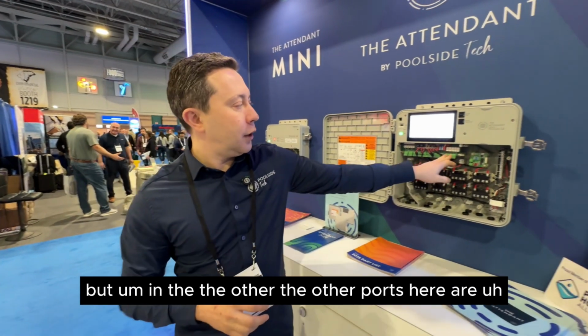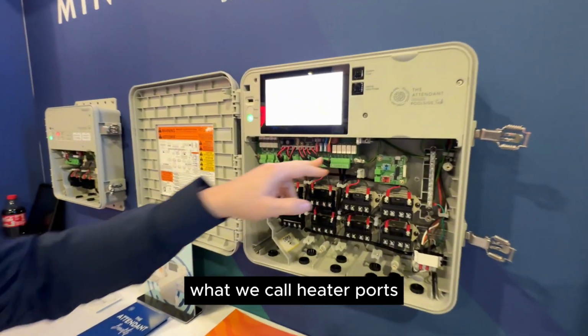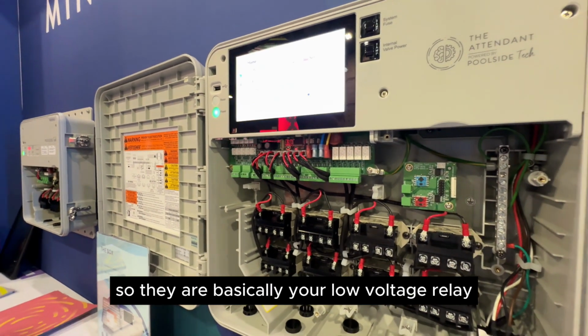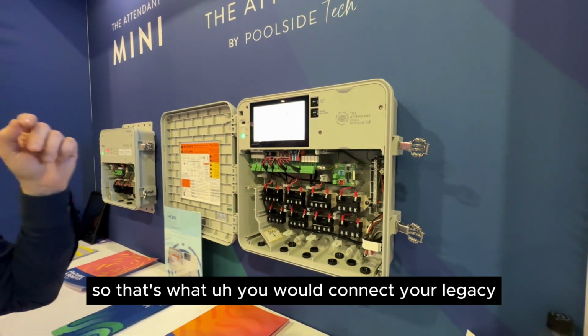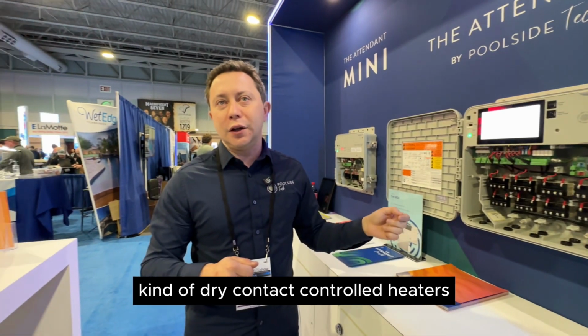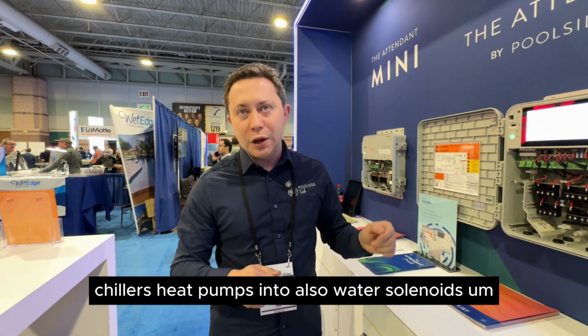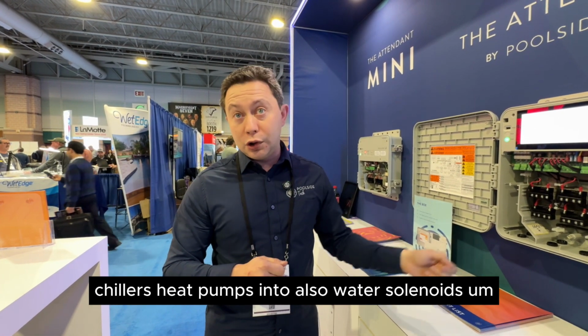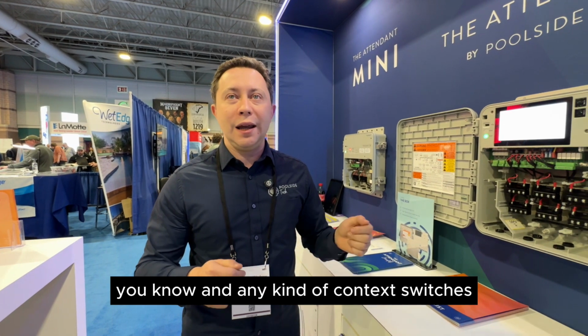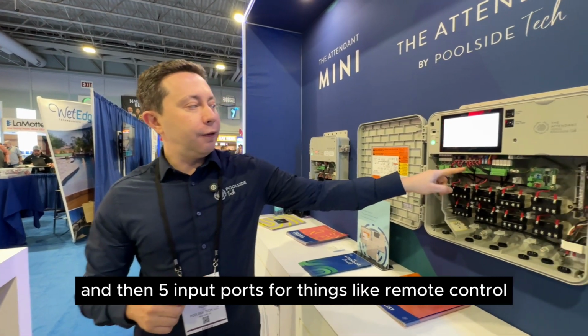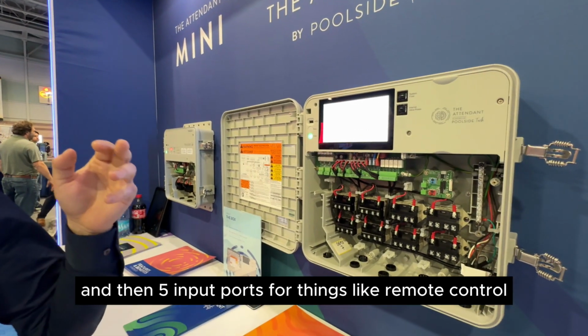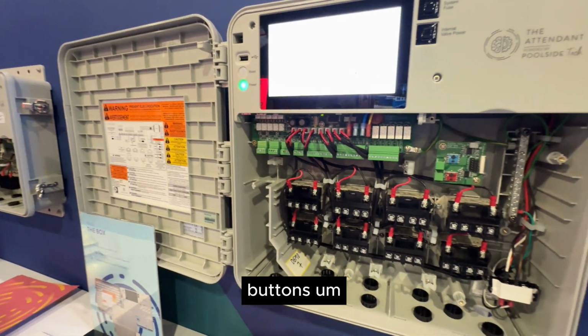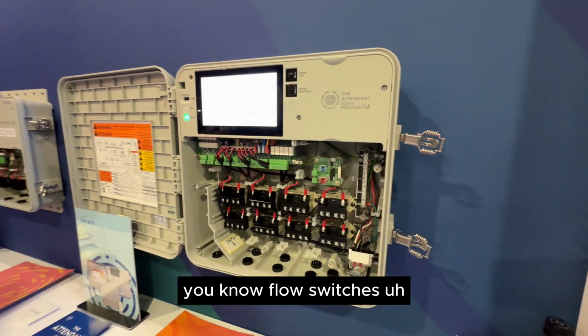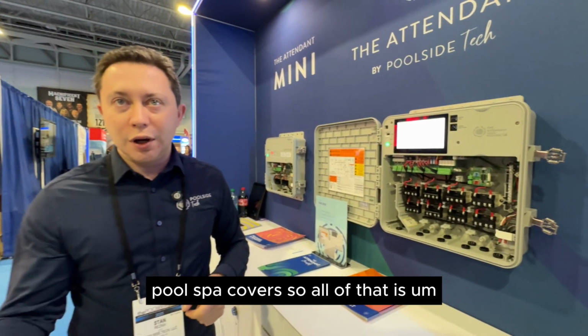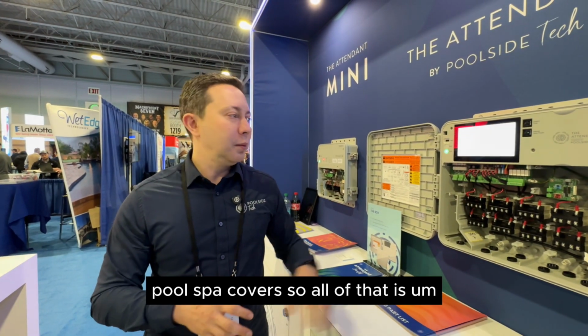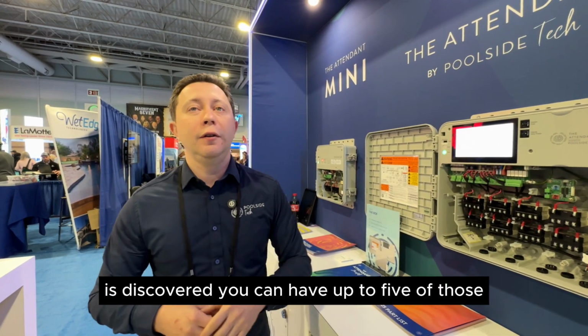The other ports here are what we call heater ports, so they are basically your low voltage relays. That's what you would connect your legacy dry contact controlled heaters, chillers, heat pumps into. Also water solenoids and any kind of contact switches. And then 5 input ports for things like remote control buttons, flow switches, pool spa covers. So all of that is covered—you can have up to 5 of those.